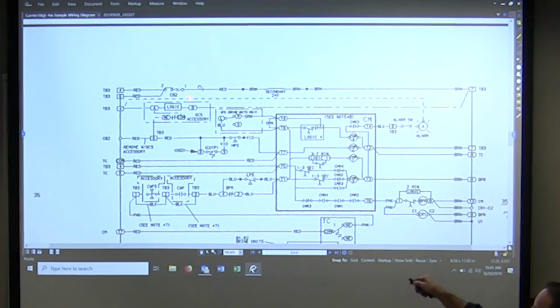So right here, what is this? It's like some sort of a circuit breaker thermal overload, so that if anything shorts as I'm switching it, I pop the fuse, I don't ruin my transformer. So because I have a circuit breaker here, I'm doing all my switching here. This is going to be my 24 volt high side. This will be my 24 volt low side. Okay, as we look at that, the common.